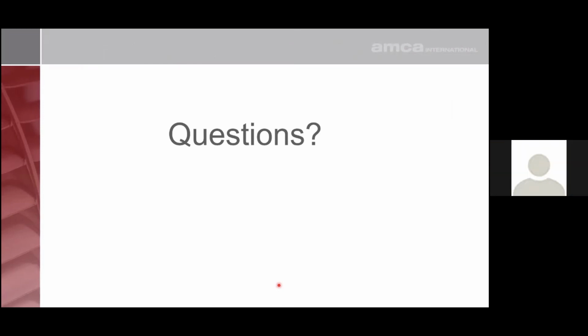We have another one from the chat. Yep. Would you be able to demonstrate the fan laws with this demonstration as well as the system effects if you had a VFD? Ooh, I've done this presentation with somebody that I was in Australia and they set up with a VFD. You have to learn the system effects demo with the new system, but you could show, yes, you could definitely show off a pitot tube traverse. You can sit there and show off how you do a fan curve. You can show off the changes in the fan curve as you increase or decrease the fan speed. And you could also show how the fan curve shape changes as you put on different ductwork configurations.